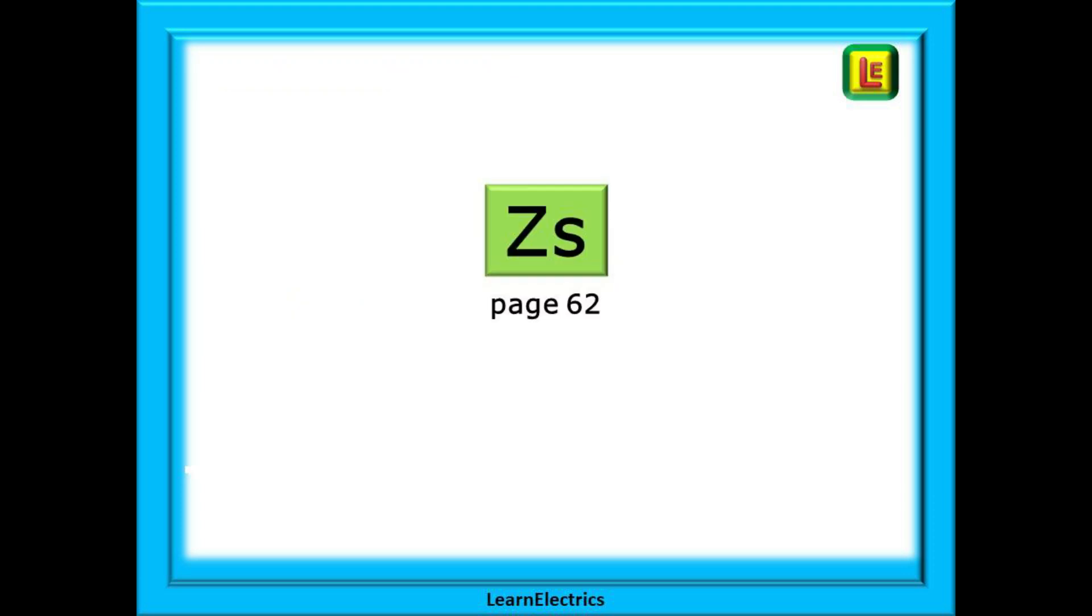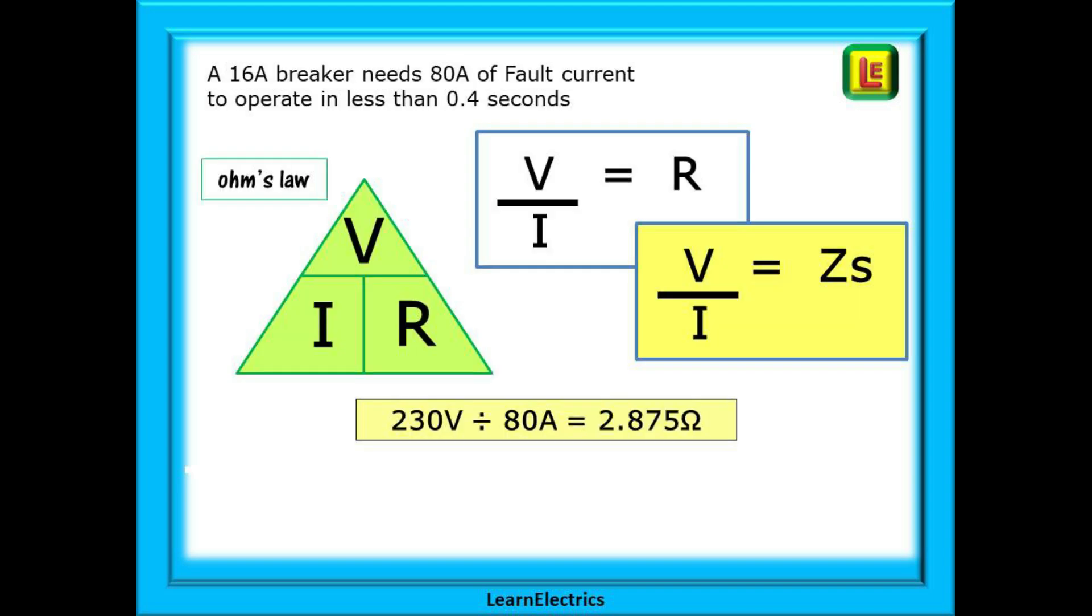Now consider ZS and find page 62 in the wiring regulations book. We could all remember Ohm's law and the equation V over I equals R, voltage divided by current equals resistance. Or we could say that V divided by current equals ZS. Using the 80 amp answer from our example question, 230 volts divided by 80 amps is 2.875 ohms.